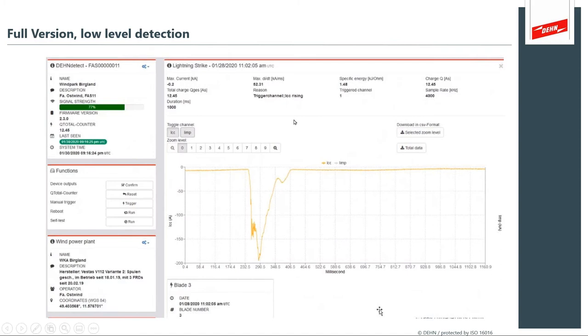This is a really interesting part — an event that was only a low-level ICC event. You can see it's low-level, around 200 amps — not a tremendous amount of current, but it actually persisted for some amount of time. That's what's really interesting about the full-version data. It gives you a scientific measurement of actual events and logs them so you can come back later and make decisions.